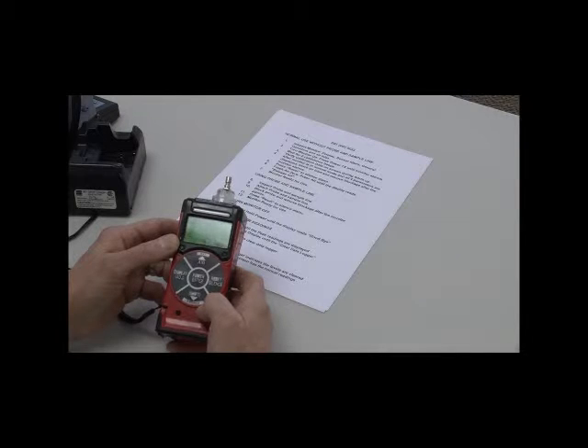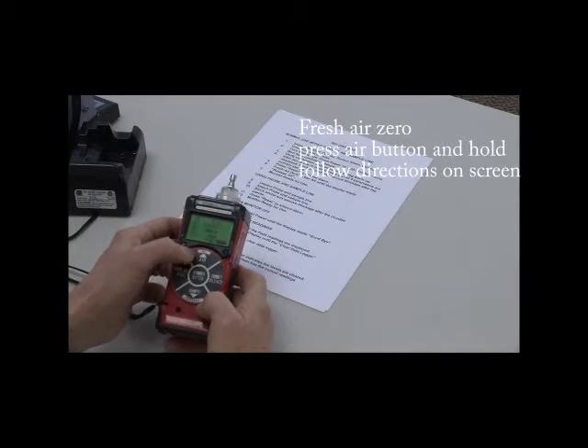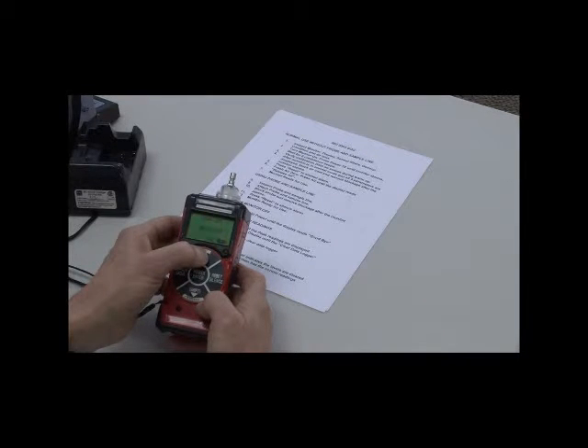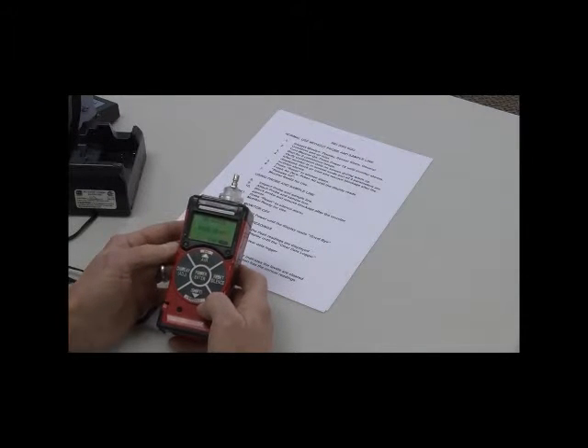At this point, I'm going to do a fresh air zero to ensure that the sensors are working properly. So I'm going to press and hold the air button until it tells me to release it. Now it's telling me to hold the air key. It's adjusting to zero. It beeps and says release the air key to finish adjusting to zero.